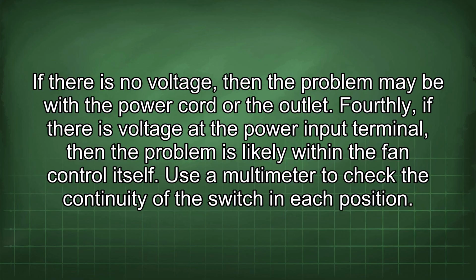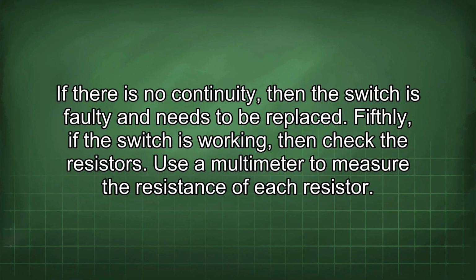Fourthly, if there is voltage at the power input terminal, then the problem is likely within the fan control itself. Use a multimeter to check the continuity of the switch in each position. If there is no continuity, then the switch is faulty and needs to be replaced.